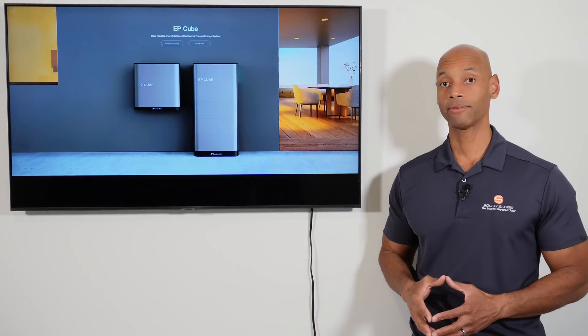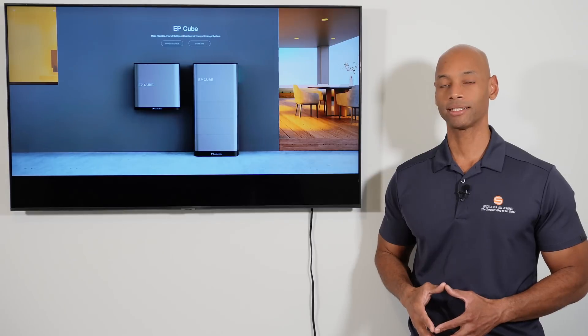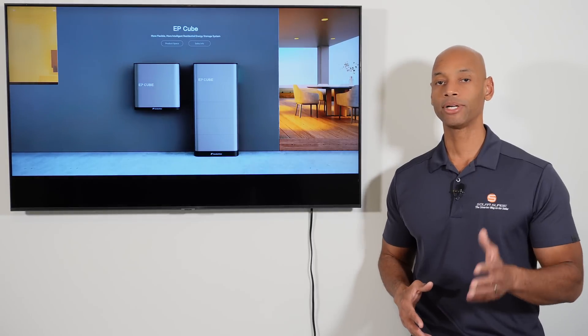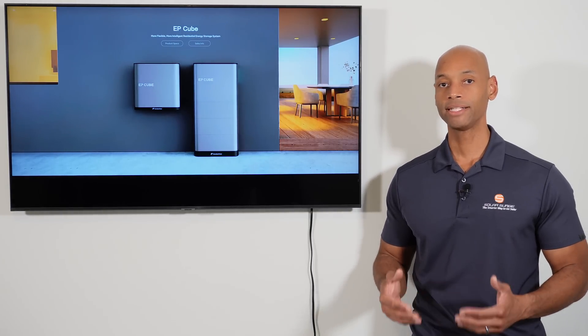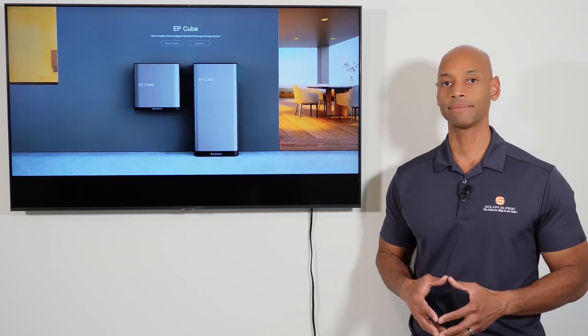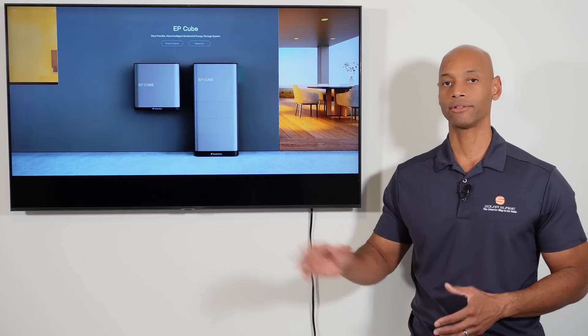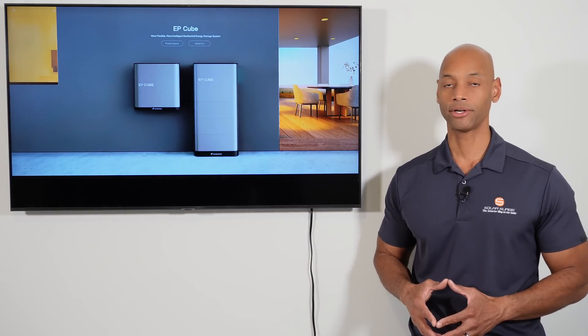In terms of power rating, each inverter assembly is rated for 7.6 kilowatts of AC output power. That 7.6 kilowatt size is very common because it's the maximum AC system size that can be back-fed via a circuit breaker into a standard 200-amp electrical panel, which is what you'll find in most US homes.